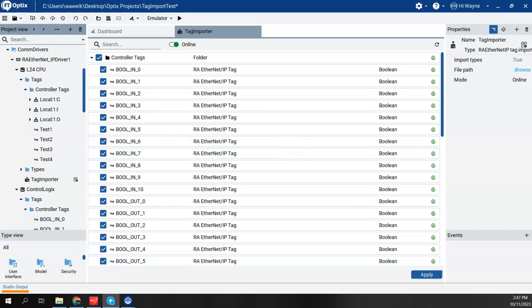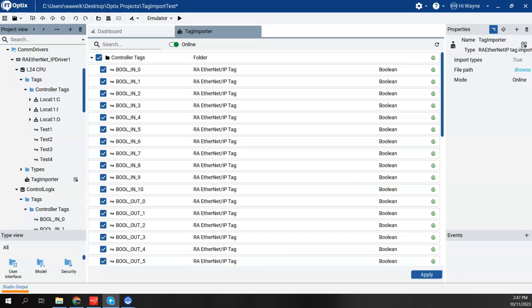So a few other notes about connecting to a Logix controller. One, you do have to be at version 32 firmware or higher in order for Optix to work with the Logix controller. So the RA Ethernet IP driver will support Logix controllers that have firmware version 32 or higher.